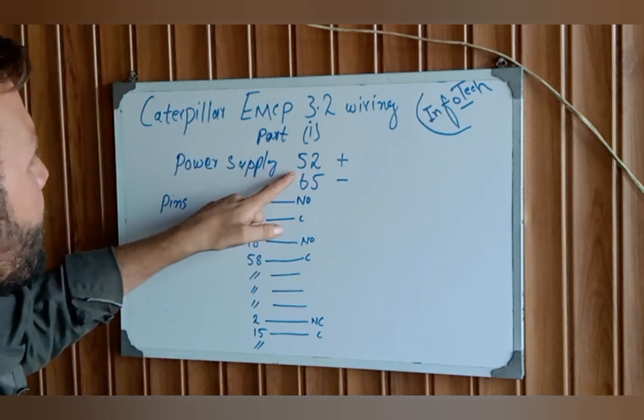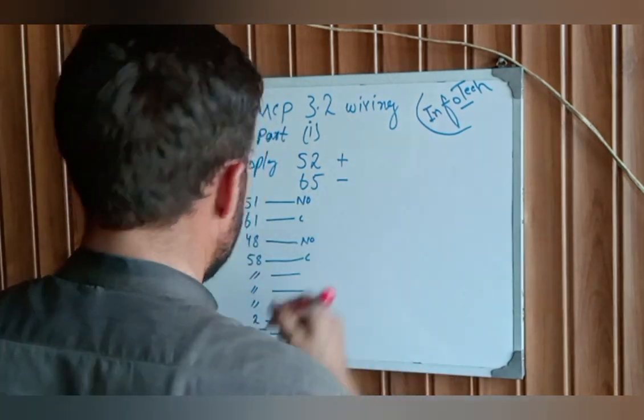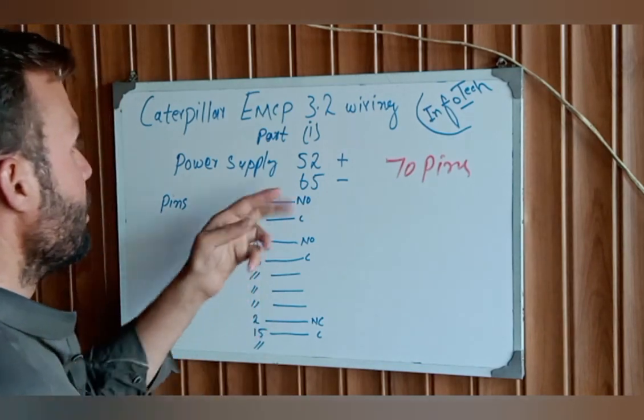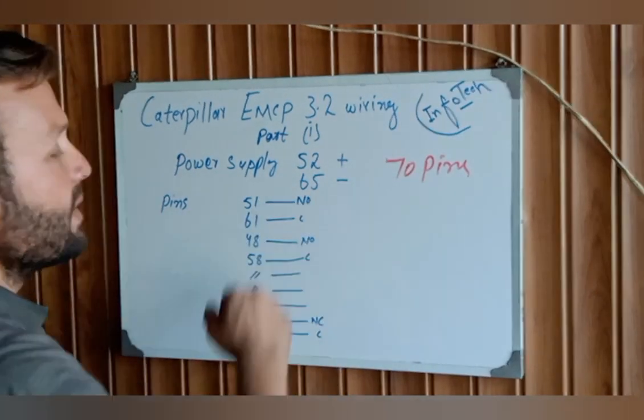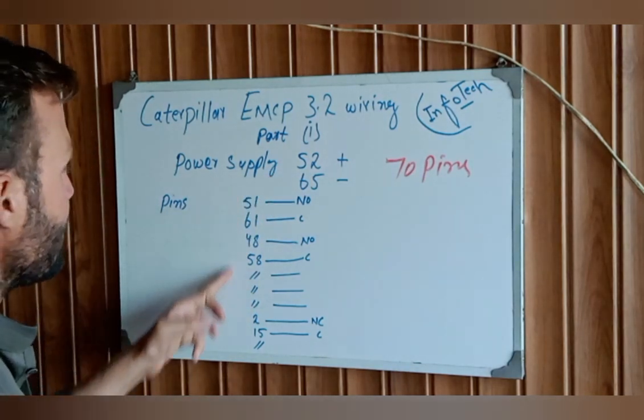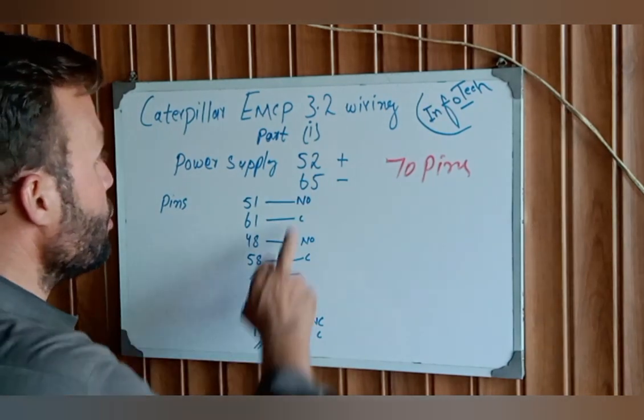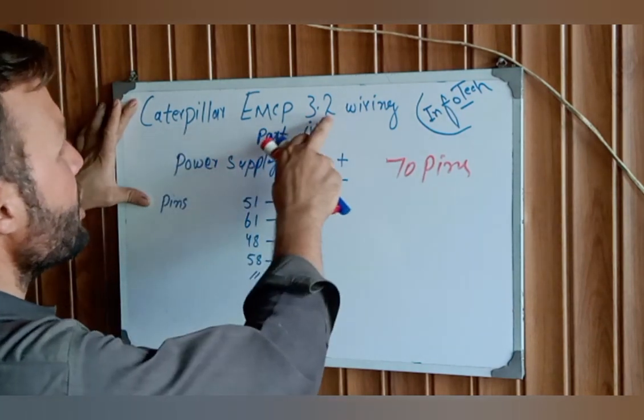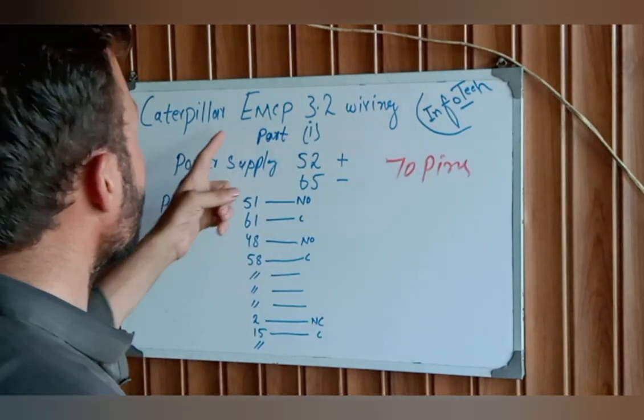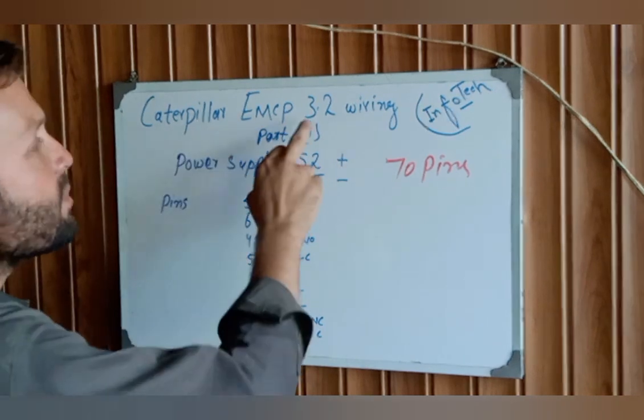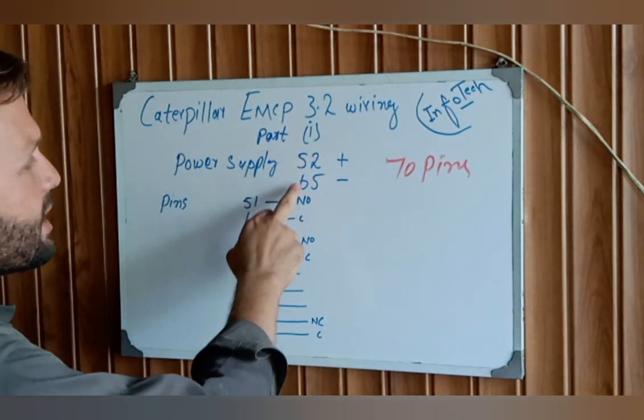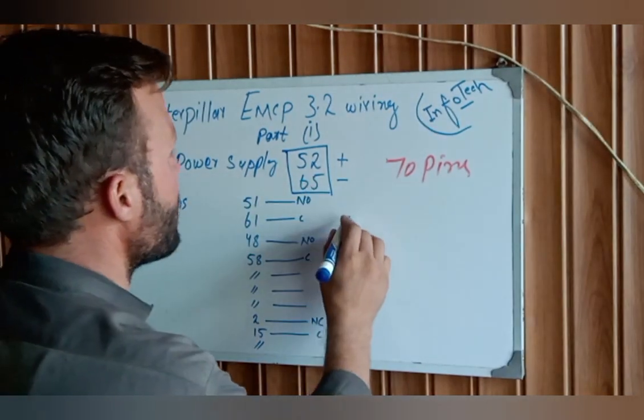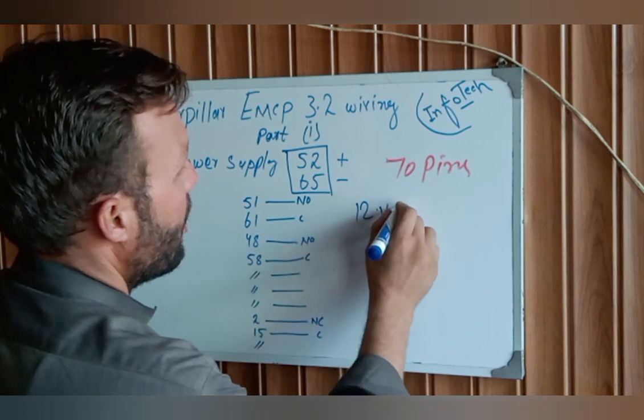First of all, for wake up and turning on, main supply is on the big side, the 70 pins connector. You remove the pin connector and look inside, you'll note these numbers. Pin 52 is your positive supply and pin 65 is your negative supply for turning on the EMCP 3.2 wiring. If your EMCP 3 is not turning on, you check this supply first.